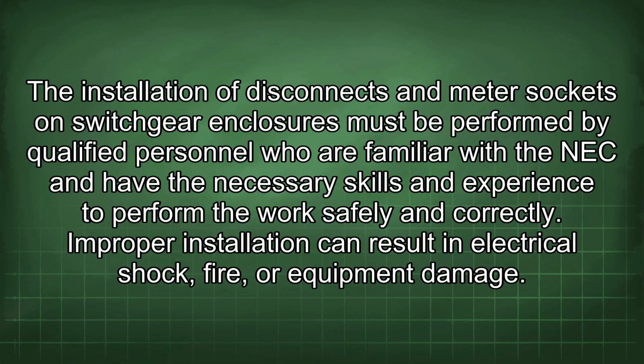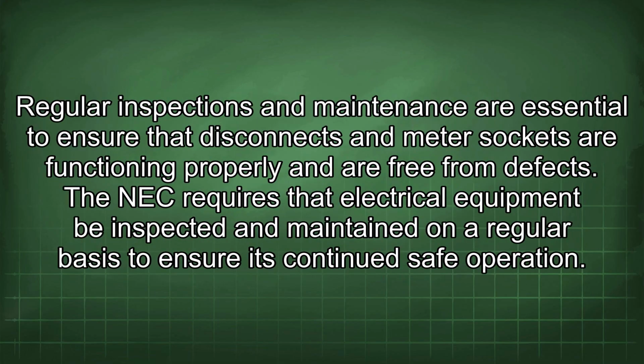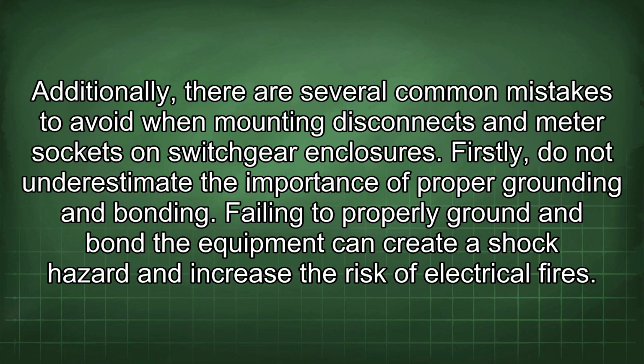Improper installation can result in electrical shock, fire, or equipment damage. Regular inspections and maintenance are essential to ensure that disconnects and meter sockets are functioning properly and are free from defects. The NEC requires that electrical equipment be inspected and maintained on a regular basis to ensure its continued safe operation. Additionally, there are several common mistakes to avoid when mounting disconnects and meter sockets on switchgear enclosures. Firstly, do not underestimate the importance of proper grounding and bonding. Failing to properly ground and bond the equipment can create a shock hazard and increase the risk of electrical fires.